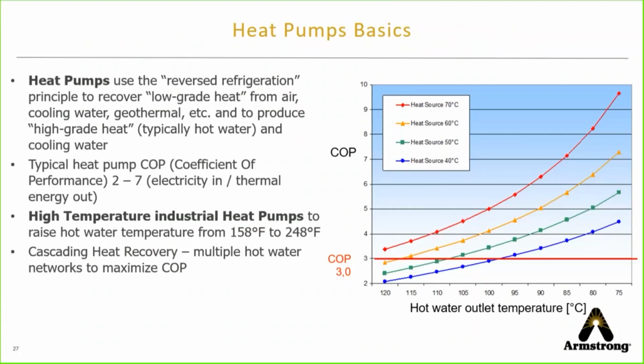Temperature ranges typically from 158 degrees up to high temperature heat pumps using R1233ZDE as the refrigerant, up to 248 degrees. And technologies are being worked on and developed now, such as water as the refrigerant, to even generate low pressure steam and even higher temperature hot water in the future.